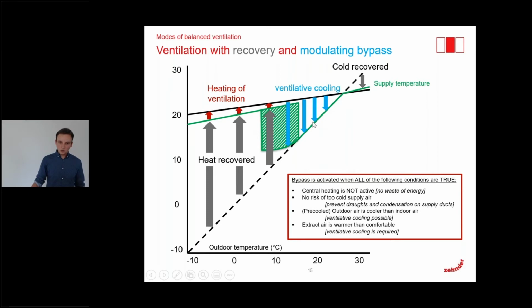And then when we go a little bit further to the green area, this is the working range of the modulating bypass. So at lower temperatures, we have more heat recovery and less bypass activation, and at higher temperatures, we have more bypass activation and less heat recovery.